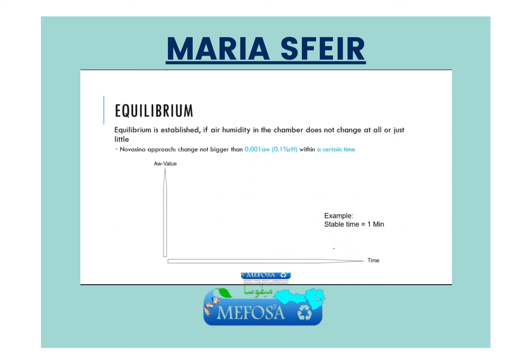First, we put the sample inside the cup, okay? And we put the cup inside the machine. The water activity in the cup, of the food, will start increasing. The machine will start measuring the water activity. The machine will measure the water activity of the product at a certain point and again after 1 minute. If the difference between these two points is over 0.001, the sample is not stable. The water activity is not stable. So we need to wait a bit longer, and when the difference in water activity is less than 0.001 during 1 minute, we can say that the product is stable. This is the stability time, SST. So we have a stable water activity.